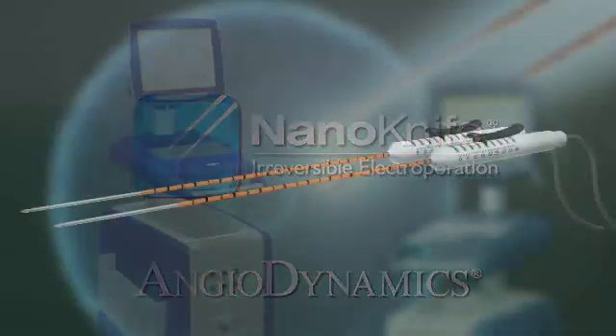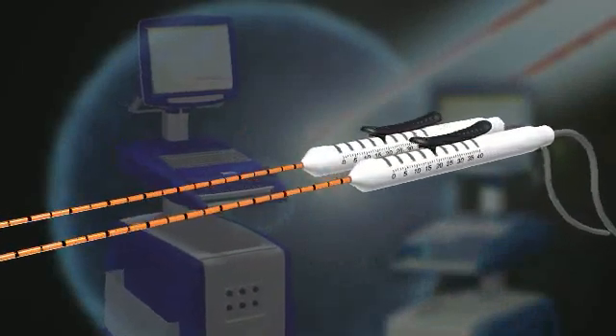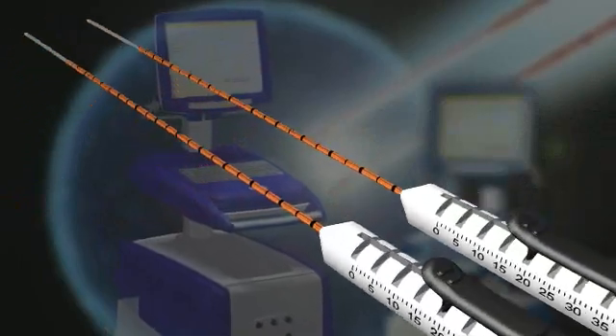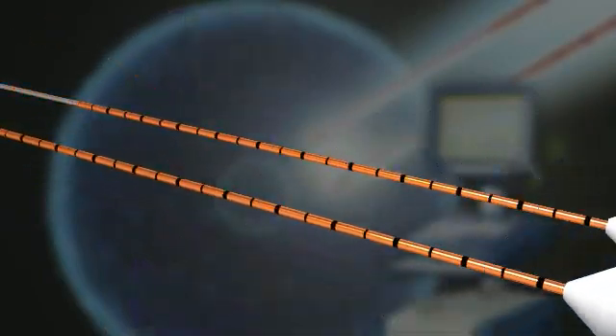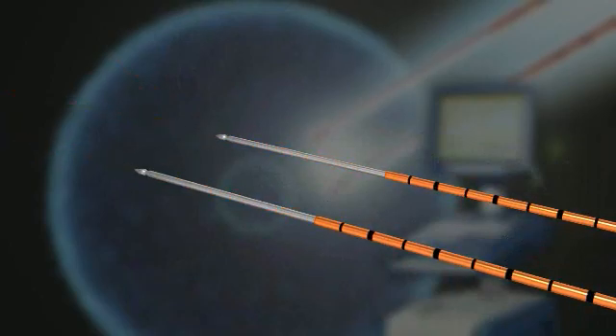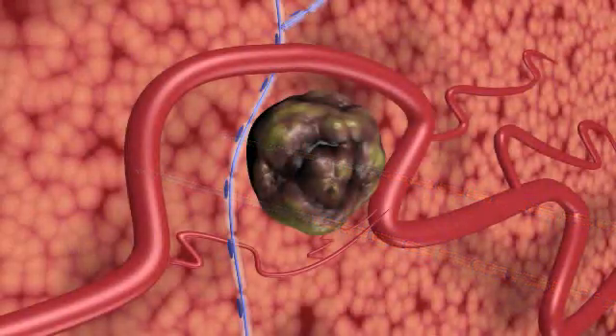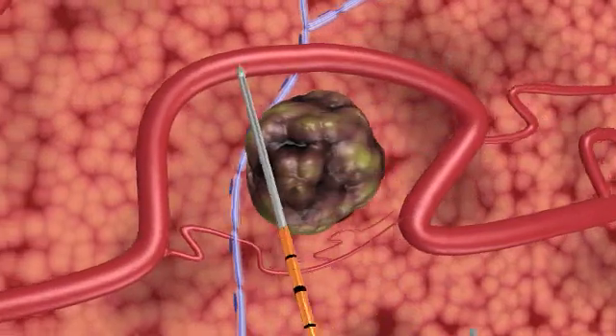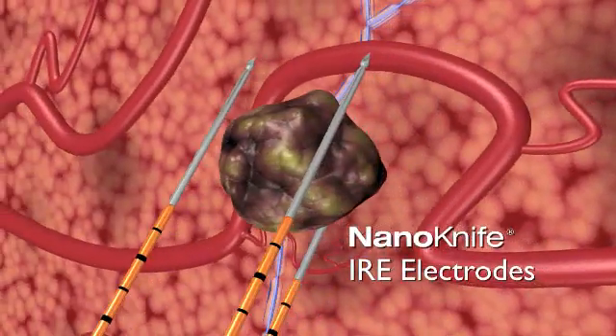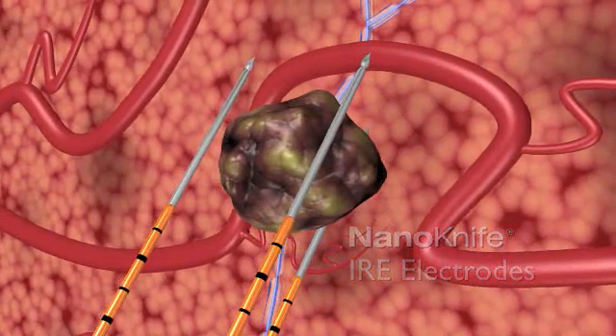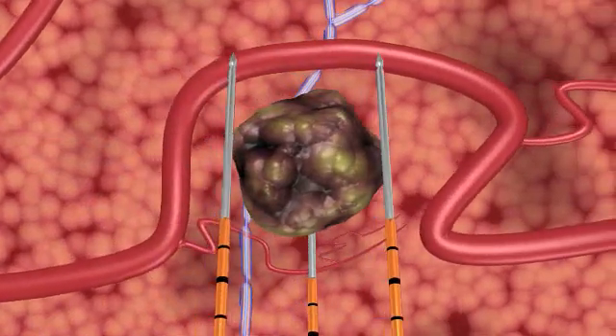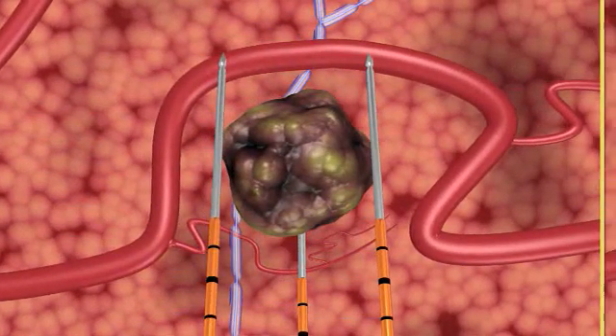The Nanoknife IRE surgical ablation system is the first to use irreversible electroporation, also known as IRE, to ablate soft tissue. Two or more Nanoknife IRE disposable electrodes are positioned in or around the area to be ablated, and an electrical field is created between them in a series of microsecond pulses, which induces cell death in the encompassed soft tissue.